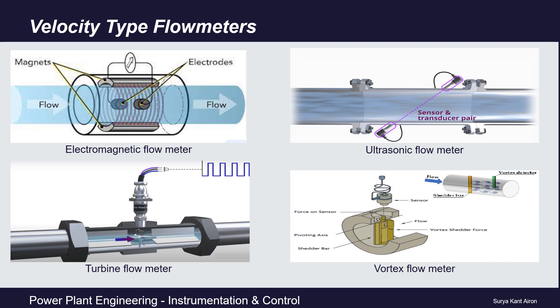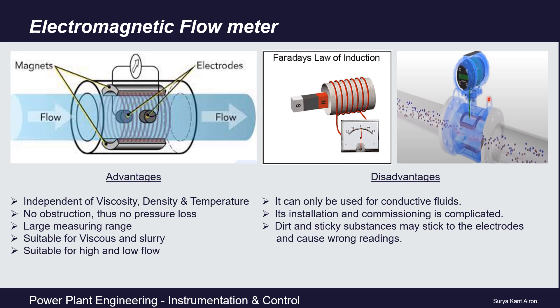Electromagnetic flow meters are based on Faraday's law of electromagnetic induction. Due to conductive fluid flowing through the pipeline, an induced EMF is generated, and this change in induced EMF is calibrated as the fluid flow rate. These are suitable for viscous and slurry fluids. The disadvantage is that they are useful only for conductive fluids, and installation and commissioning is complicated. The best feature is no flow obstruction and no pressure loss.